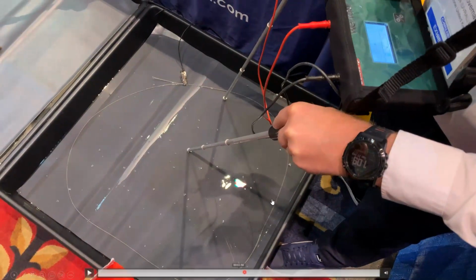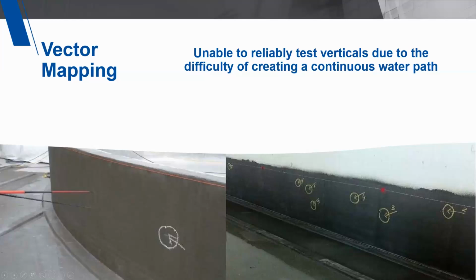So there's the wire, there's the flooded water path, these are the probes. Now, most ELD testing agencies that use this method don't use it on a vertical surface. It can be done within its limitations, it's just not really feasible. The equipment manufacturer in the United Kingdom will tell you, do not use this method on a vertical surface. But again, within its limitations, it might be possible.